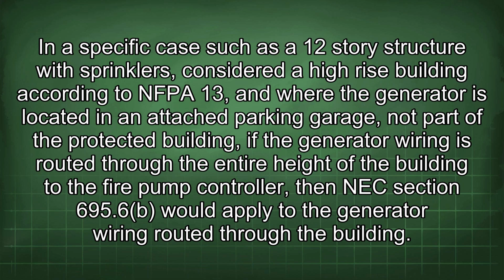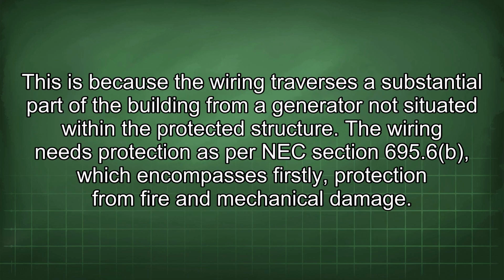In a specific case such as a 12-story structure with sprinklers, considered a high-rise building according to NFPA 13, and where the generator is located in an attached parking garage, not part of the protected building, if the generator wiring is routed through the entire height of the building to the fire pump controller, then NEC section 695.6 would apply to the generator wiring routed through the building. This is because the wiring traverses a substantial part of the building from a generator not situated within the protected structure.